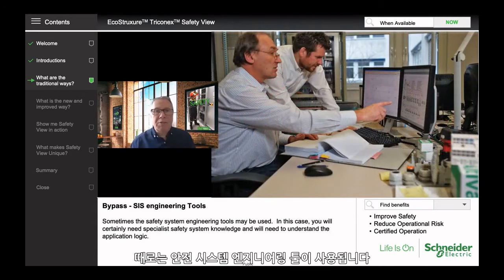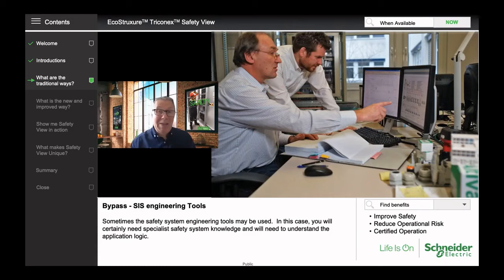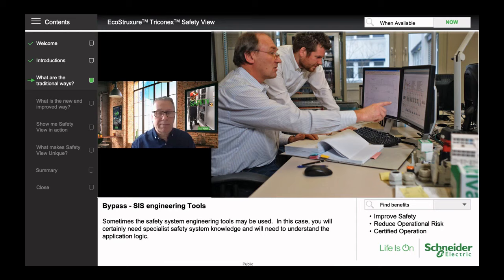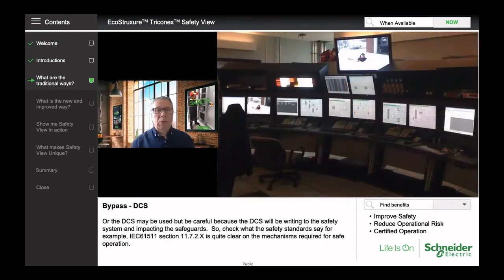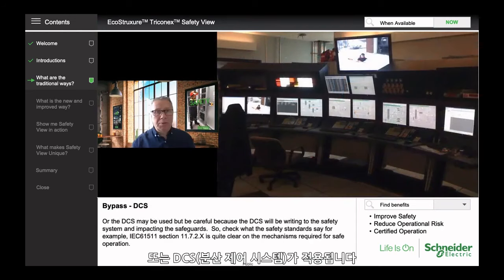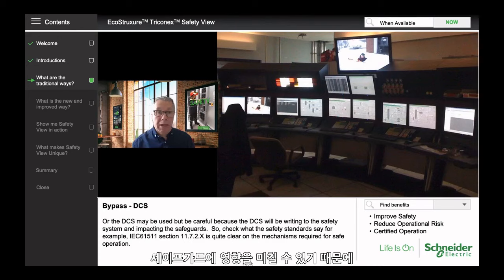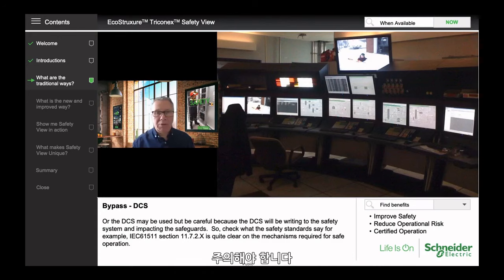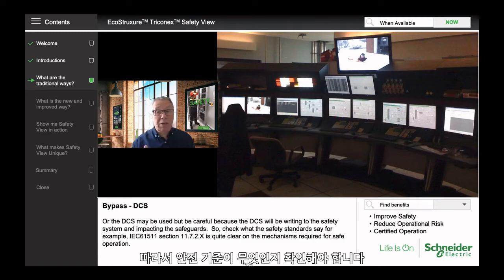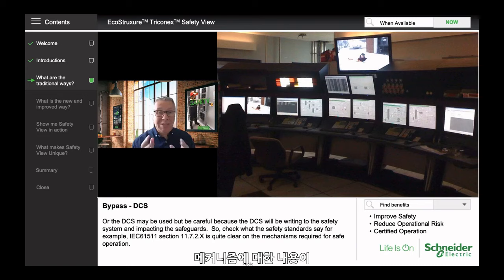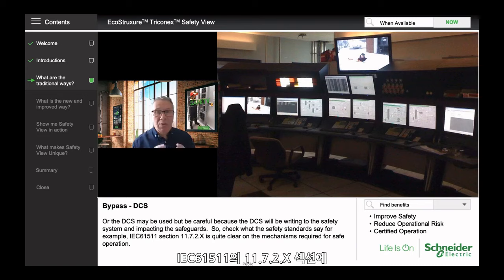Sometimes the safety system engineering tools may be used. In this case, you'll certainly need specialist safety system knowledge and you'll need to understand the application logic. Or the DCS may be used, but be careful — the DCS will be writing to the safety system and therefore impacting the safeguards. Check what the safety standards say; for example, IEC 61511 Section 11.7.2.X is quite clear on the mechanisms required for safe operation.